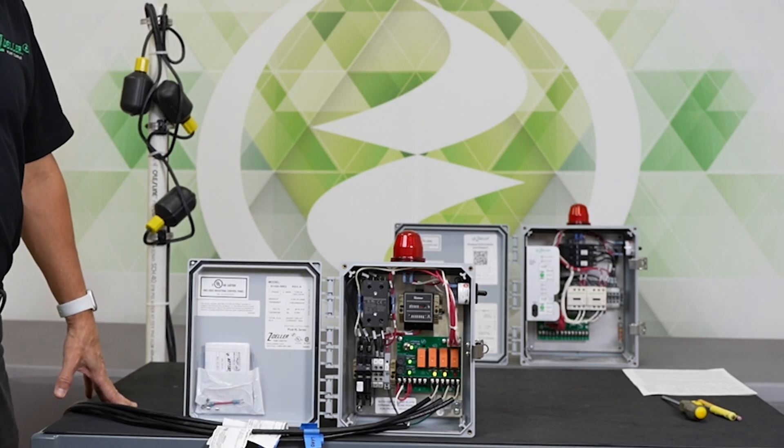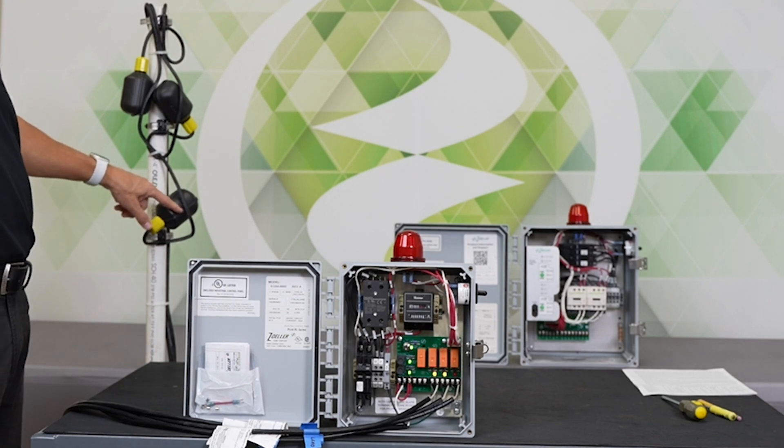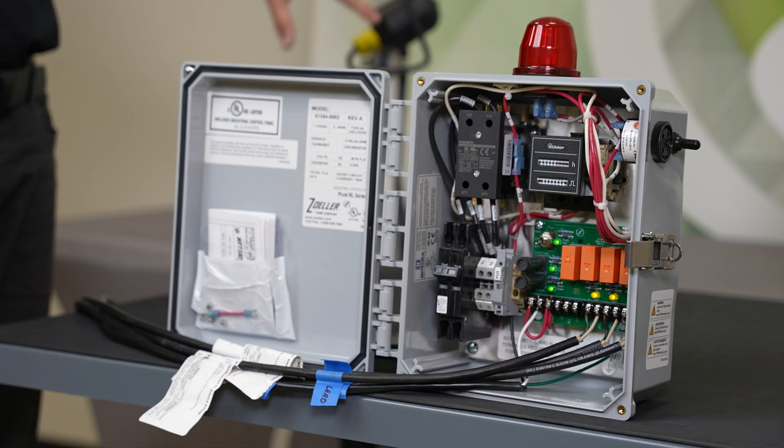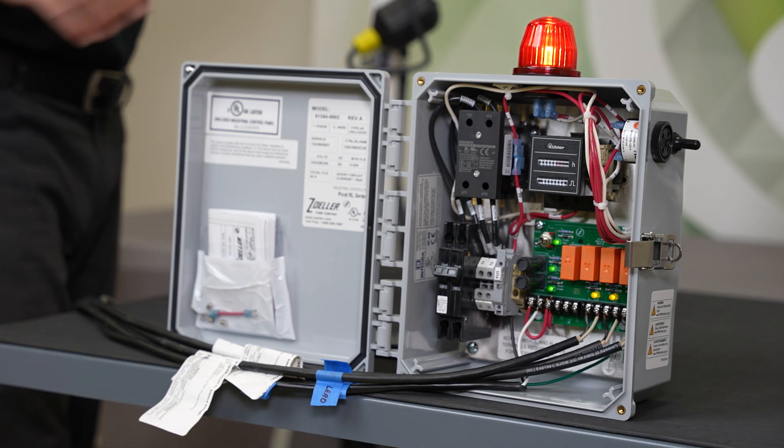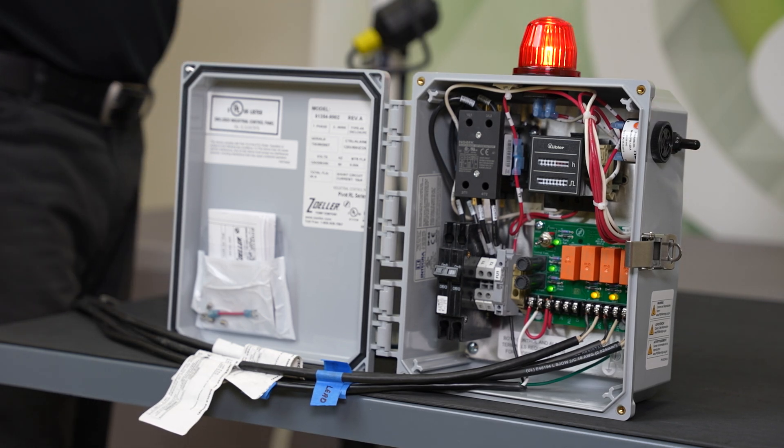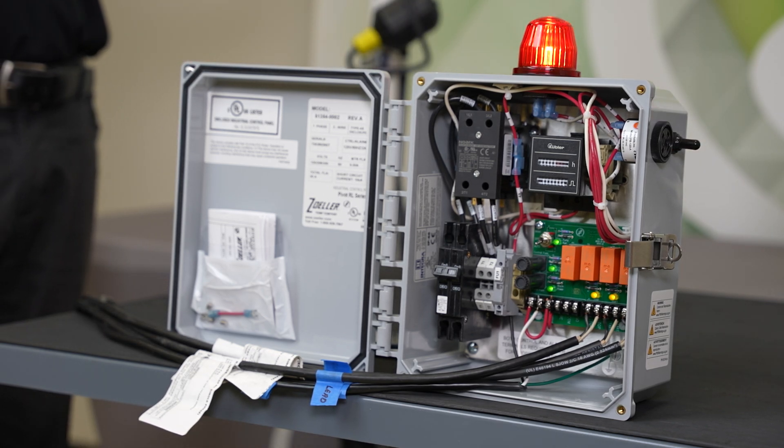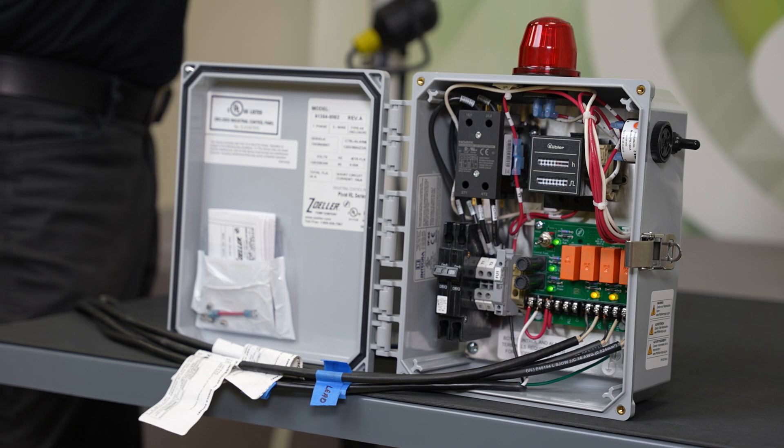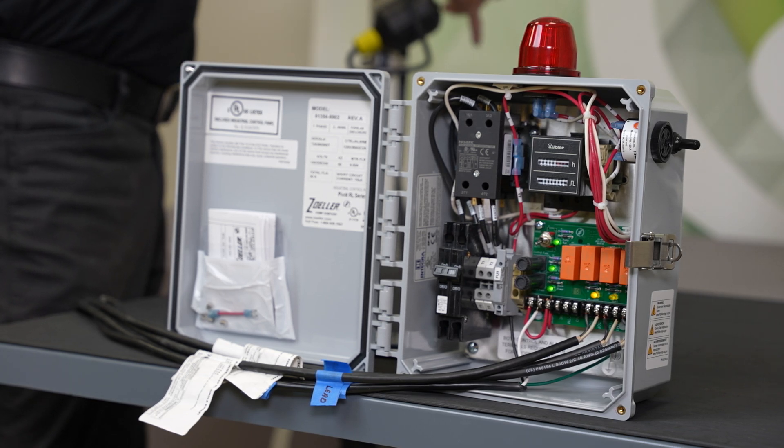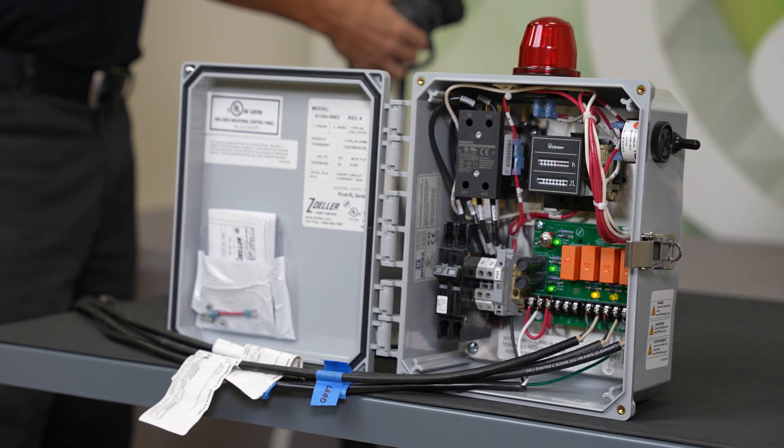In order to demonstrate the high water alarm, I have my stop float and my start float tethered up, and I'm going to lift the high water, silence the high water. Now the high water goes down, alarm goes away, and then we'll lower our start float, and when I lower my stop float, the pump will turn off.